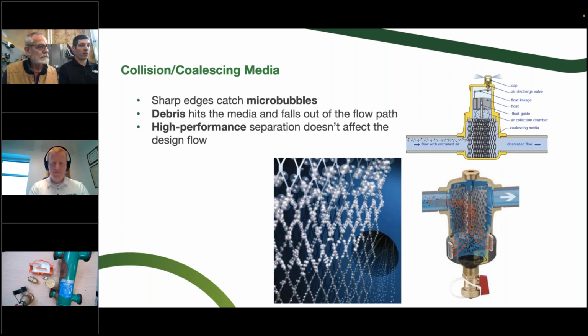Okay, so let's say we want to go beyond an air vent to a high performance device that's actually going to catch little micro bubbles of air as they're passing through portions of the piping with the circulator on. We need to graduate to something like an air separator. So if you look at the cross section here, it's still just an air vent at the top, same linkage and everything. It floats on a pin right there, so it stays right in the center of the separator. But we've added a collision media. Coalescing media is another word we use for it, and that means to gather.